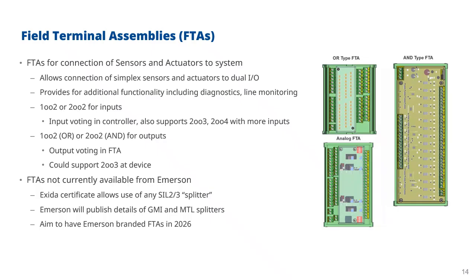So what we need to do is have a way of having the simplex sensor be split out to two physical inputs, and also then on the other side, when the outputs come out of the dual output modules, they have to be ORed down or ANDed into a single output to control whatever the output device is. So that's what the field terminal assemblies do: the ANDing or ORing of the inputs and the outputs in order to be able to use a dual control system, but with simplex sensors and actuators.